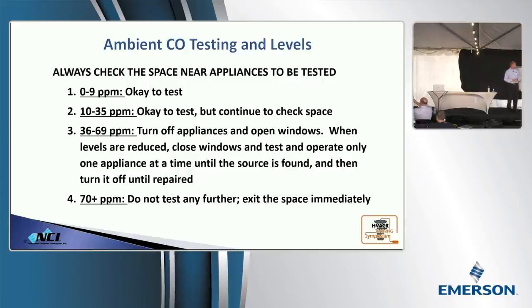Now, as you dig a little bit deeper and you get into 10 to 35, at that point, you need to start squirming a little bit. Start figuring out why. 0 parts per million is the only acceptable level from vented appliances. You should never have CO in the space from a vented piece of equipment, because if you do, it's spilling. And you guys are going to see sometimes it can turn from a situation that may not look very bad into something that is extremely dangerous, like that. And I'd have never believed it when I first went through my first combustion class over 20 years ago. And then I saw it happen. I'll share that with you shortly.